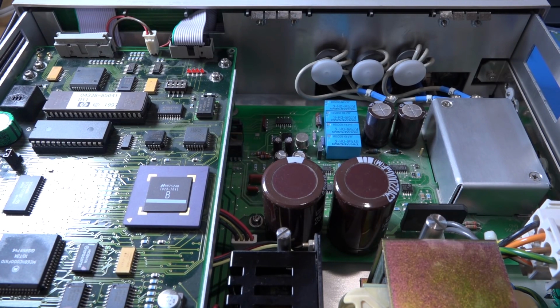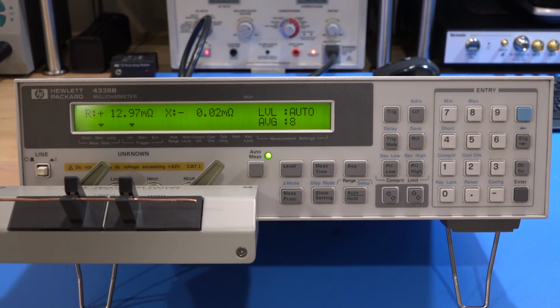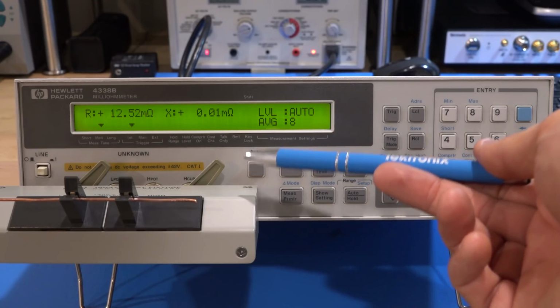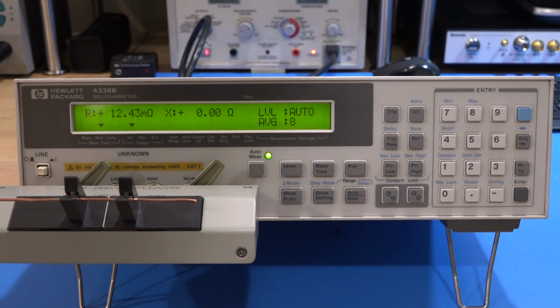So now that it's all back together, I'll just put the cover on it. And here's the unit up and running, and it seems to be nicely functional. So right now I have this fixture connected to it. This is the HP16047D. It's the wrong fixture for this instrument. It's not the one you're supposed to be using, so I can't get very reliable measurements out of it. This is really for an LCR meter, but of course it still can do some measurements.